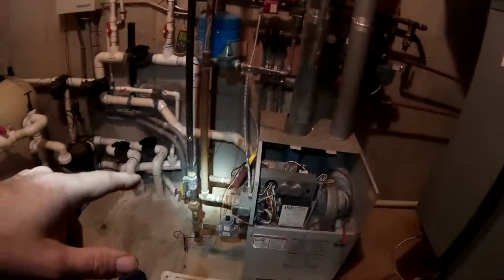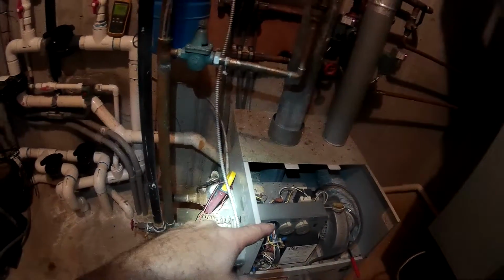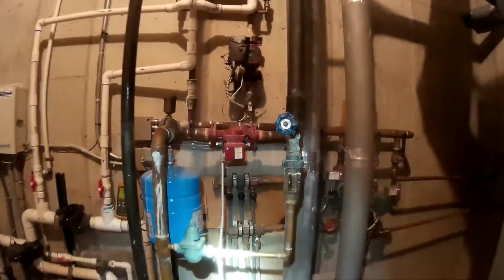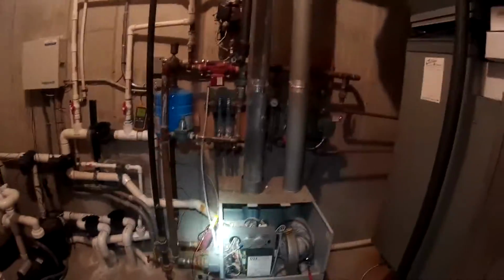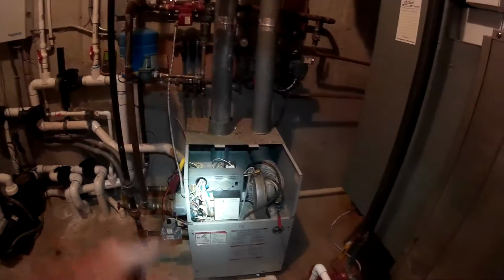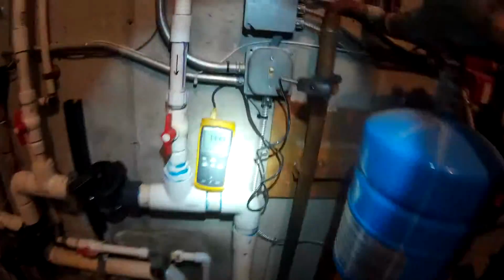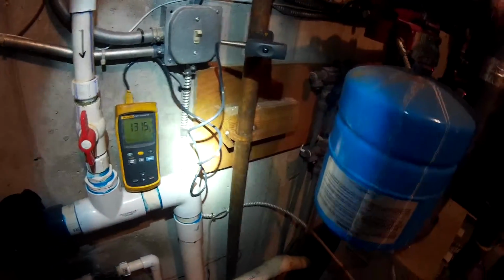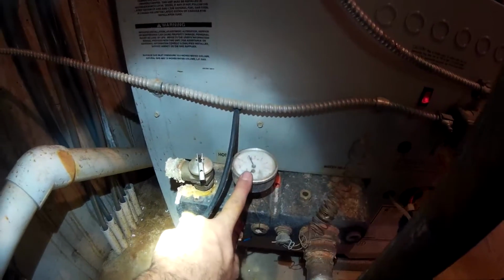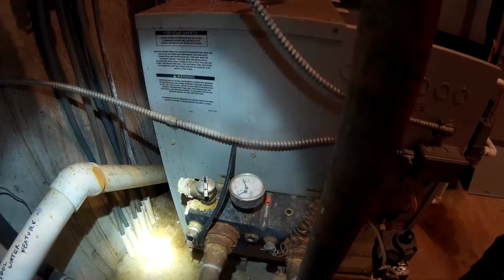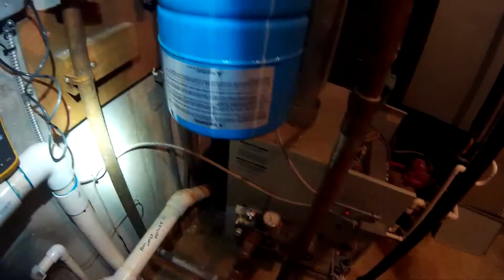So what I'll do is I'm going to order a TNP, an operating switch, operating dial, new TNP. I'm going to have to replace that pump too because that pump was making noise. And clean the blower wheel on the inducer. So this is just a quick little video about boiler temperature operators, how to troubleshoot them with your temp clamp on the supply pipe. Most of the time these Tridicators, temperature pressure gauges, see this one's sticky, sometimes they're off, so what I do is I hook up to the pipe and then I adjust my operator off pipe temperature instead of relying on the temperature on the Tridicator. It's just more accurate.